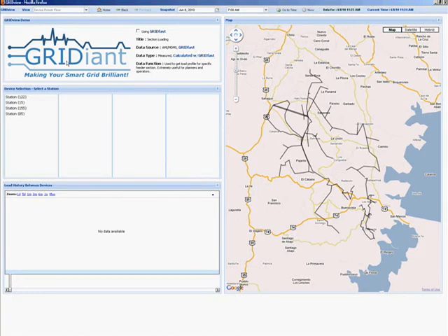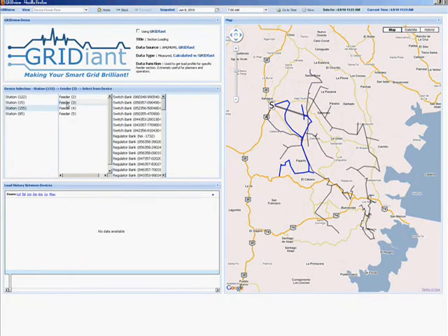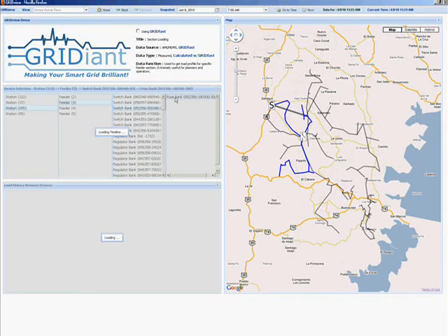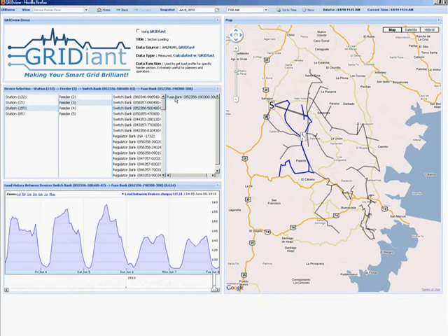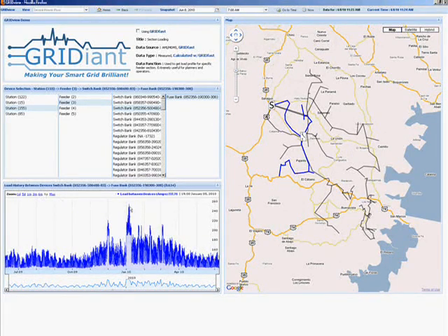If we go in here, we'll pick a station and a feeder, and I'm going to grab this switch bank here and this fuse bank. Alright, good. And so if we look at the year's worth of data, it's showing a peak load of about 260 amps. Whereas in the last week or so, that section was seeing 140 amps, or maybe even less. So if you're using a load flow program and it's telling you 260, or if it's even using quarterly peak loads and it's telling you 220, when really you're at 140, that's a substantial difference.